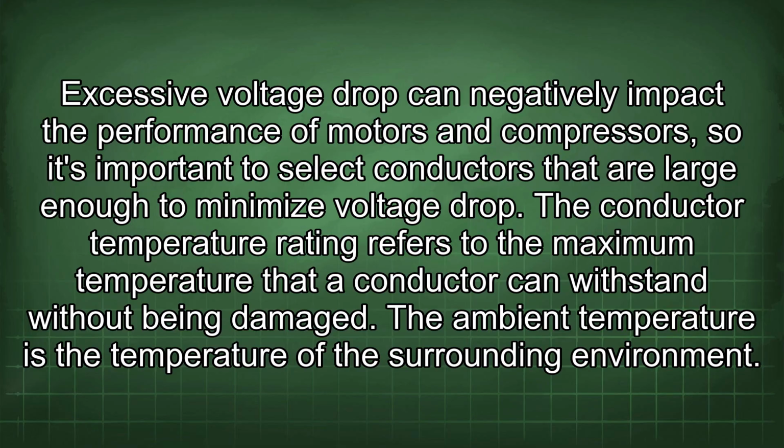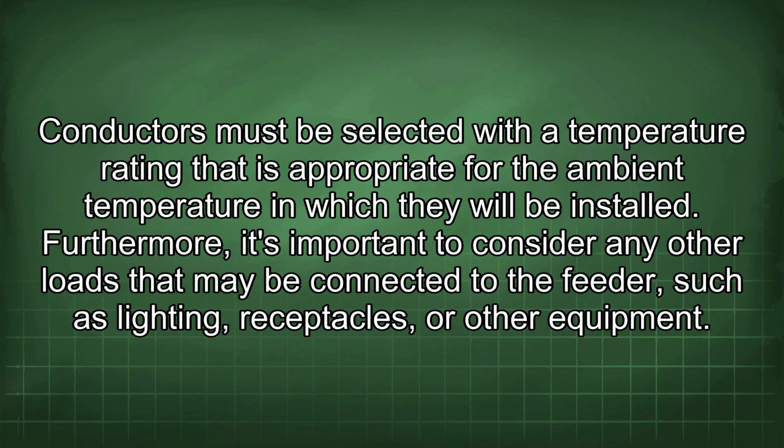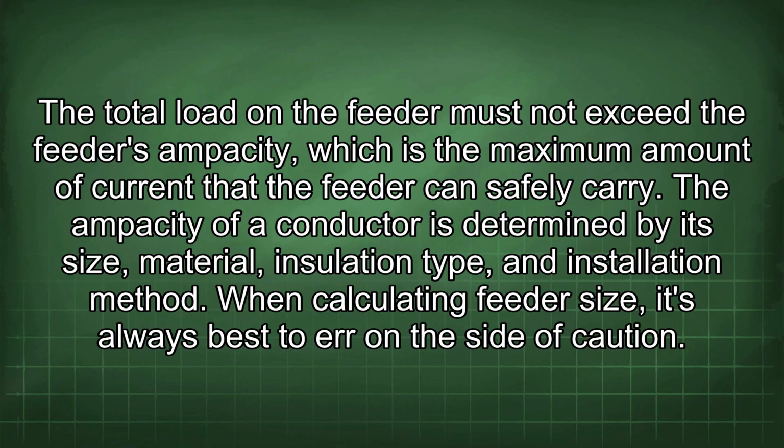The conductor temperature rating refers to the maximum temperature that a conductor can withstand without being damaged. The ambient temperature is the temperature of the surrounding environment. Conductors must be selected with a temperature rating that is appropriate for the ambient temperature in which they will be installed. Furthermore, it's important to consider any other loads that may be connected to the feeder, such as lighting, receptacles, or other equipment. Total load on the feeder must not exceed the feeder's ampacity, which is the maximum amount of current that the feeder can safely carry. The ampacity of a conductor is determined by its size, material, insulation type, and installation method.